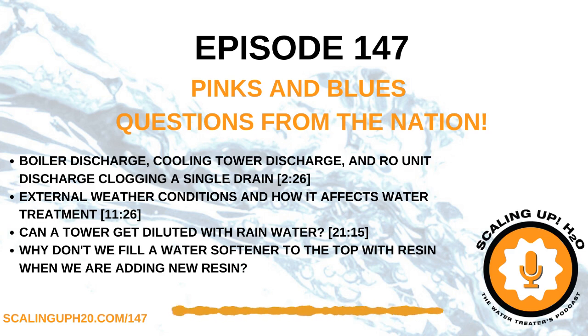This is the reason we have a fan in a cooling tower. I've trained so many water treaters over the years, and most people think at first glance that the fan is what cools the water inside a cooling tower. Folks, that's not the case—the fan isn't meant to cool the water. The fan is meant to get all that saturated air out of the cooling tower so we can replace it with less saturated air, which can absorb more heat, evaporate more water vapor into it, and then get that air out of the system.